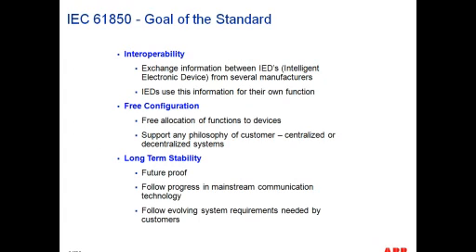And as we went over during our introduction to IEC 61850 webinar, goals of the standard include interoperability, the exchange of information between IEDs from several manufacturers, and free configuration. The standard should allow the free allocation of functions to devices and support any philosophy of customer, whether it's a centralized or decentralized type of system. And then long-term stability, in the form of future-proofing: the standard should follow progress in mainstream communications technology. What that means is essentially having a standard with a structure such that any changes in, let's say, communications media would not affect or slow down the process of the standard.